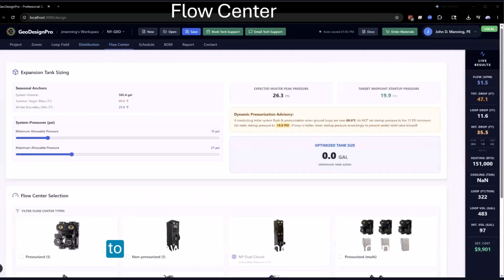Moving on to the Flow Center tab. And this is a recent addition based on expansion tank sizing. All too often, I've seen jobs with enormous expansion tanks. And the program will look at the modulus of elasticity of polyethylene pipe. More importantly, it looks at it over long term. Polyethylene pipe has the ability to creep, and if subjected to higher pressures or different temperatures over time, that pipe will respond. And that's the time frame our system behaves in months.